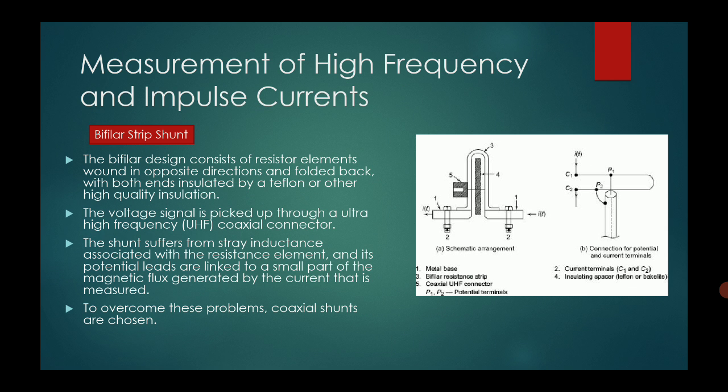For measurement of high frequency impulse currents, we can also use bifilar strip shunts. The bifilar design consists of resistor elements wound in opposite directions and folded back, with both ends insulated by Teflon or other high quality insulation. The voltage signal is picked up through UHF coaxial connectors. The shunt suffers from stray inductance associated with the resistance element and its potential leads, which are linked to a small part of the magnetic flux generated by the current being measured. To overcome these problems, coaxial shunts are chosen.